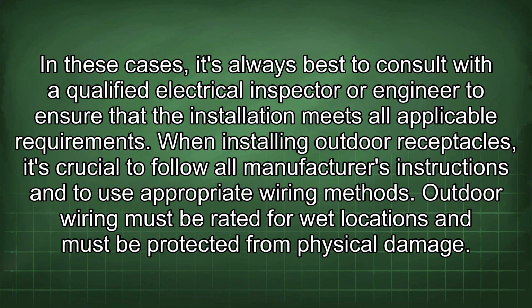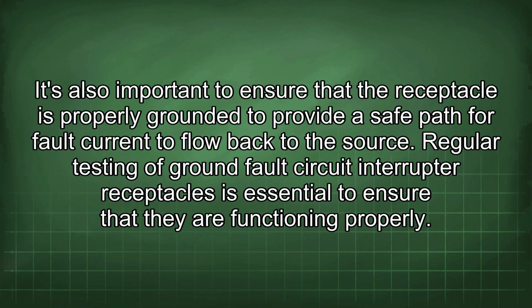When installing outdoor receptacles, it's crucial to follow all manufacturers' instructions and to use appropriate wiring methods. Outdoor wiring must be rated for wet locations and must be protected from physical damage. It's also important to ensure that the receptacle is properly grounded to provide a safe path for fault current to flow back to the source. Regular testing of ground fault circuit interrupter receptacles is essential to ensure that they are functioning properly.